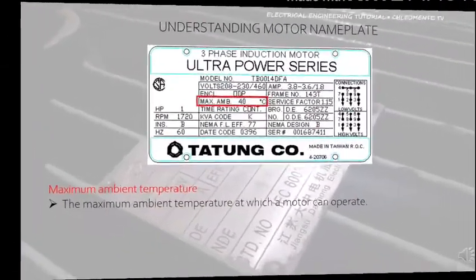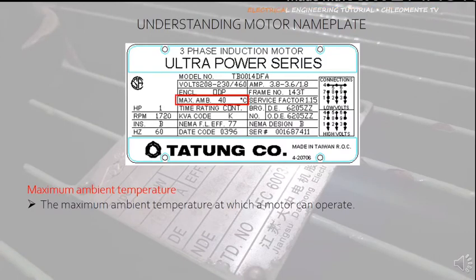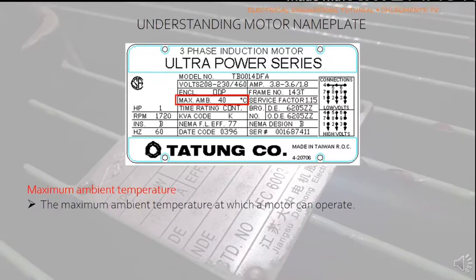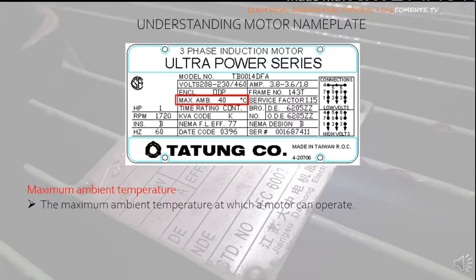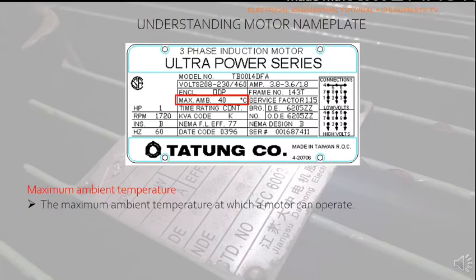Maximum ambient temperature, denoted by Max AMB: As the name implies, this is the maximum ambient temperature at which the motor can operate. Above this temperature, depending on the motor's insulation, degradation of insulation life may occur and in the long run may cause winding failure. If this data is not given on the nameplate, it is safe to assume the motor is rated at a maximum ambient temperature of 40 degrees Celsius.